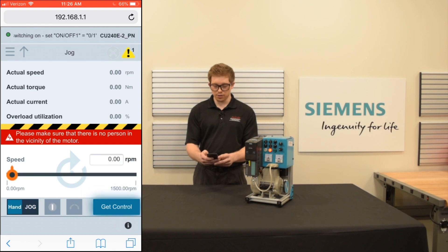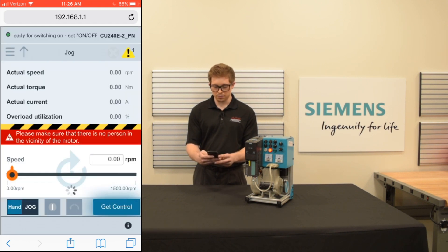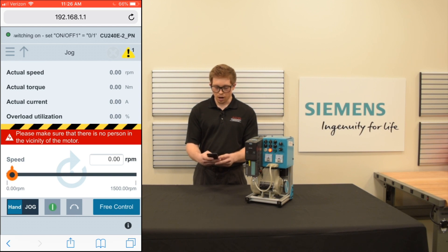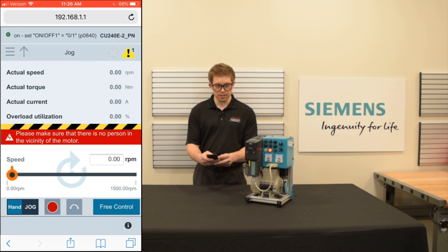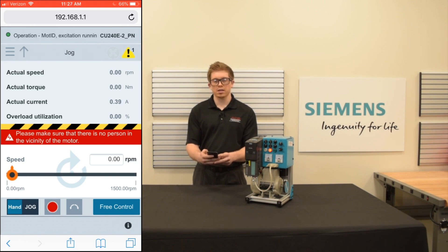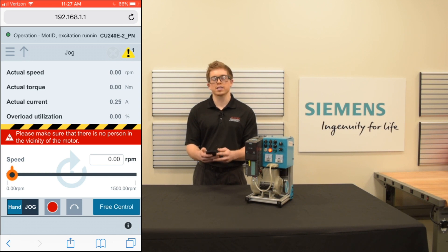Once at the jog screen, we're going to switch to hand mode. Then we're going to take control of the drive. I'm going to send a run command from my mobile device to the drive. It's now performing the identification of the motor — this only occurs the first time the drive is set up.